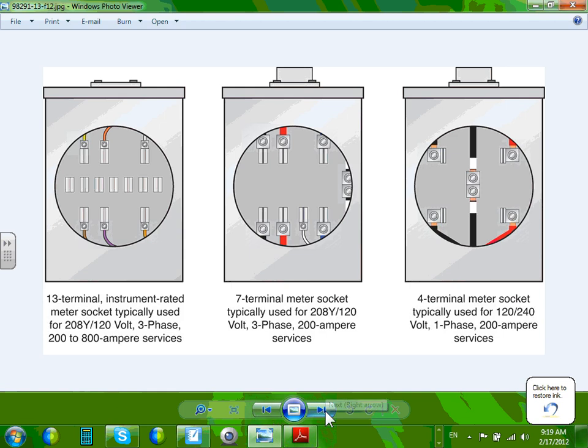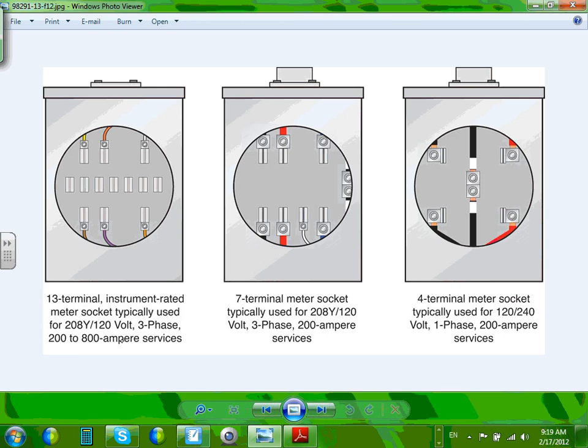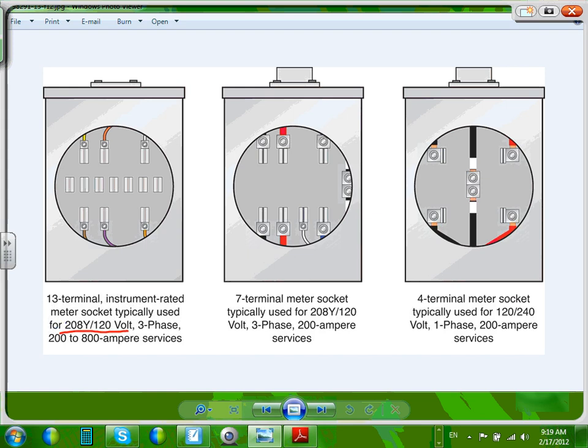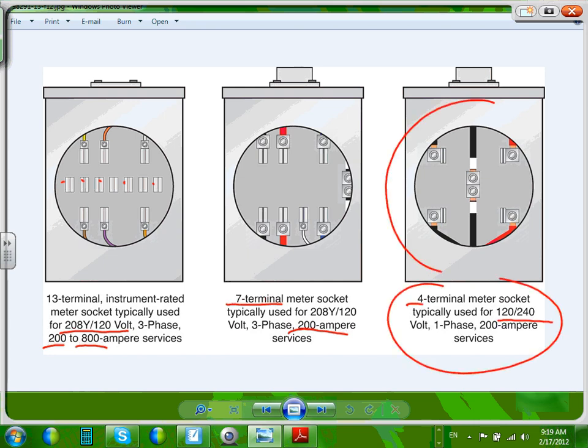Okay, meters. Most likely, guys, if you go higher than 400 amp metering, you're going to get into CT cabinets. There are a couple of pictures of nice looking meters. This one happened to be 208-120. This is my 208-120, three-phase, 200 to 800. I think they can get them to 800 at this voltage. 13 terminals. Look at all these terminals that you have here. 7 terminals get you up to 200 amps, and then you have 4 120. This is the most common one for residential. That's what you see in your residential.